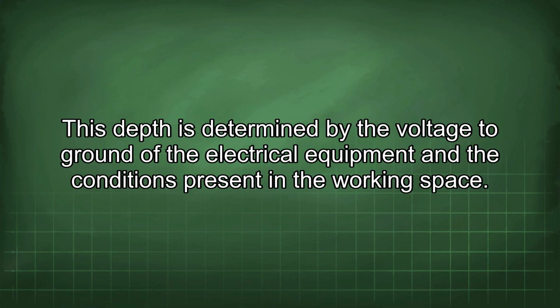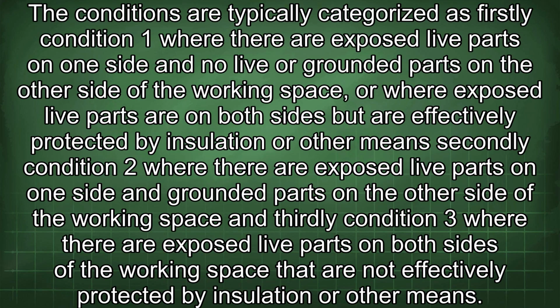equipment. This depth is determined by the voltage to ground of the electrical equipment and the conditions present in the working space. The conditions are typically categorized as, firstly, condition 1, where there are exposed live parts on one side and no live or grounded parts on the other side of the working space, or where exposed live parts are on both sides but are effectively protected by insulation or other means. Secondly, condition 2, where there are exposed live parts on one side and grounded parts on the other side of the working space. And thirdly, condition 3, where there are exposed live parts on both sides of the working space that are not effectively protected by insulation or other means.